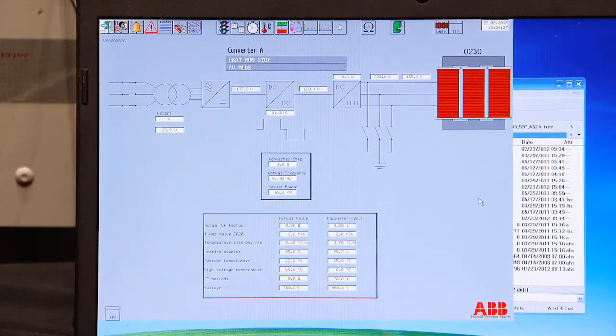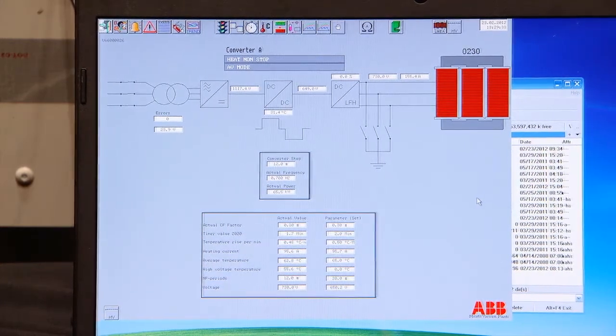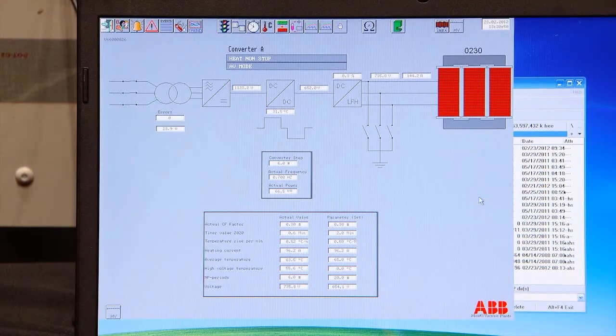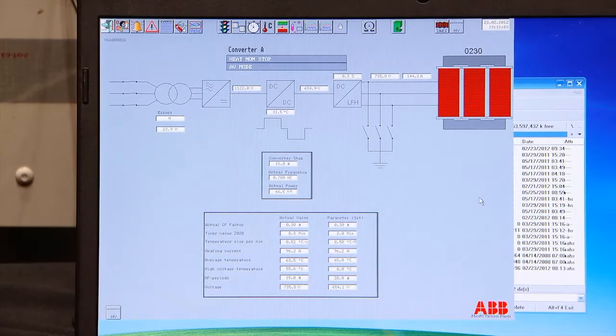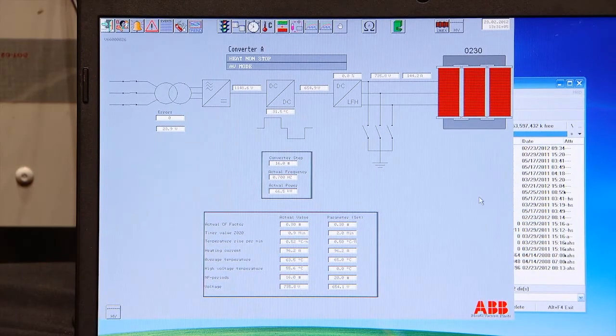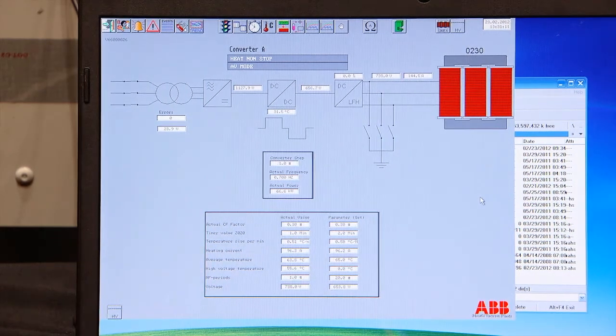In distribution transformers we heat up from dry insulation, not oil soaked, up to 120 degrees. You can set that to 5 degrees per minute or something. But you have to remember this 10 degrees per minute is not a temperature increase. It is a resistance change indicated by a temperature increase. But this resistance change has happened because of some reason. We can set it to 5 degrees. I mean, that's fair enough.